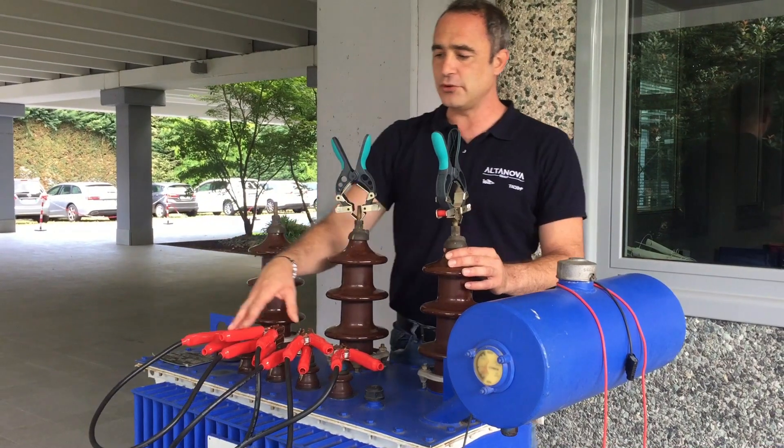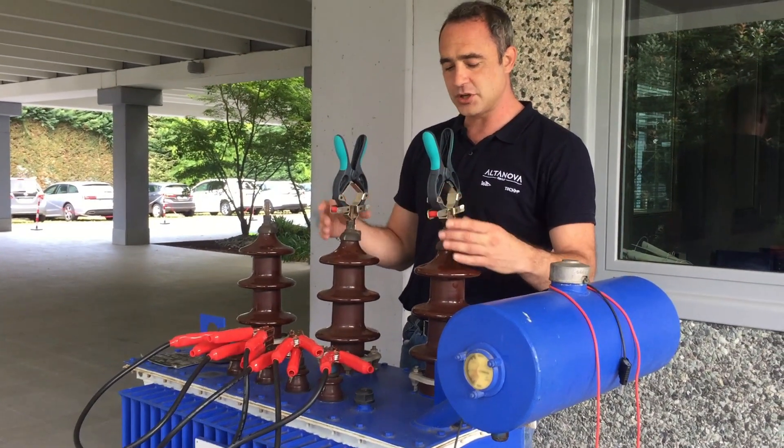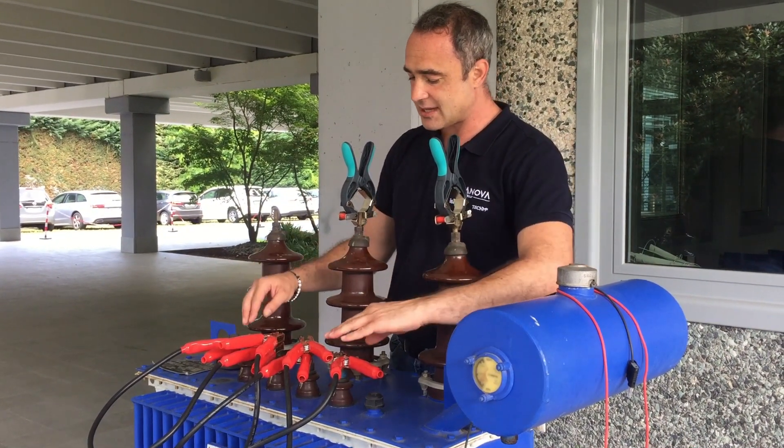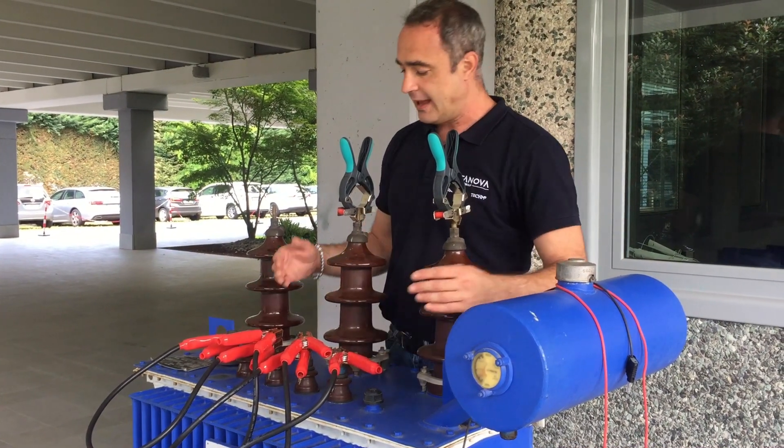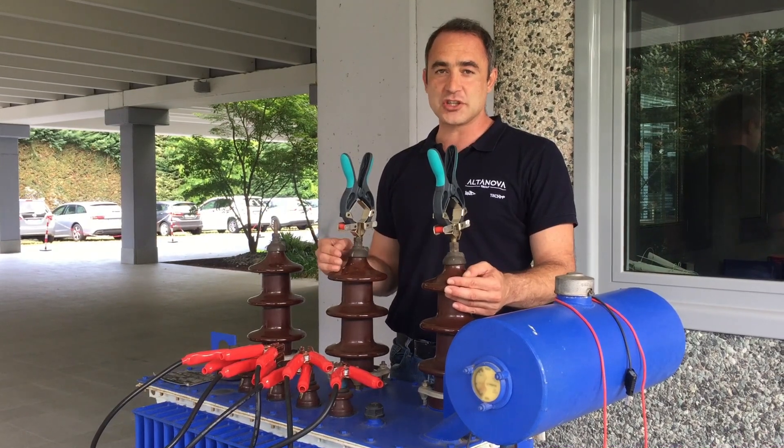That's because we're going to generate voltage on the primary side about 100 volts and the secondary side will be short-circuited. In that way what we are looking for is actually the losses in the copper.